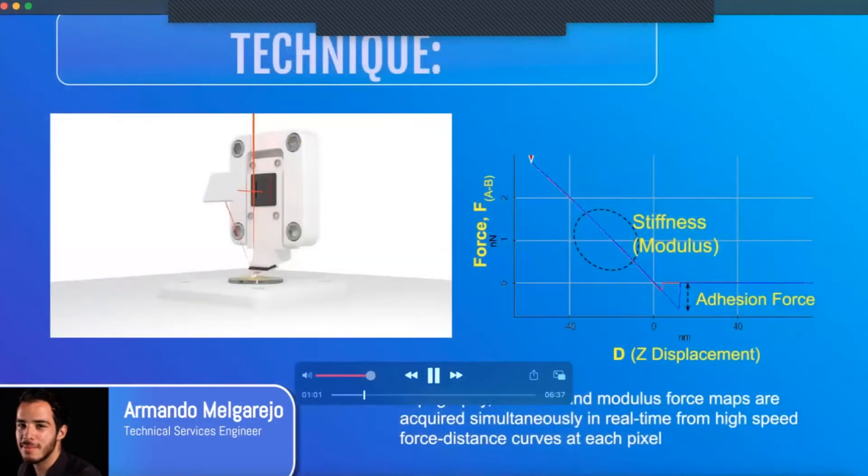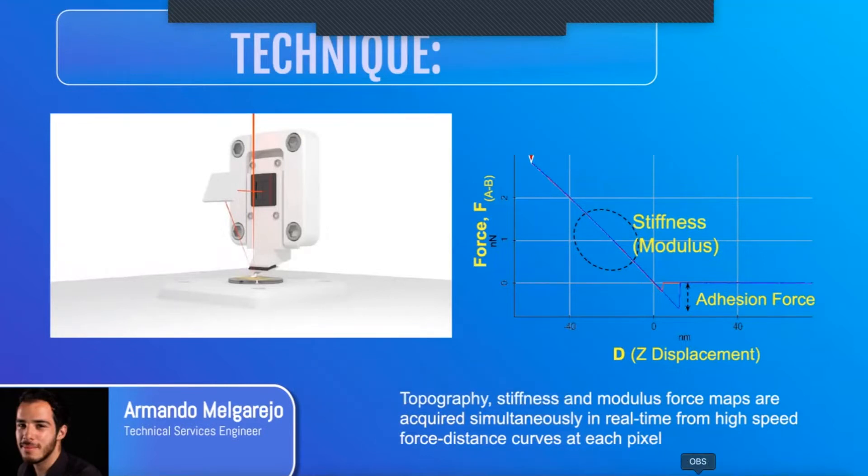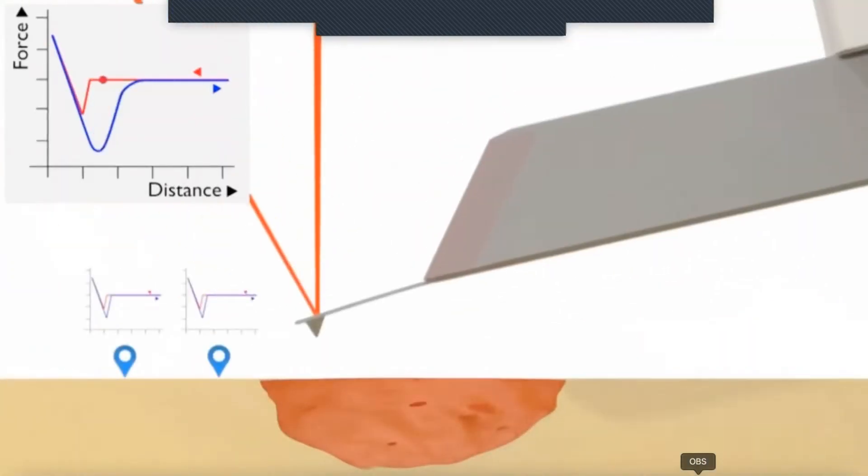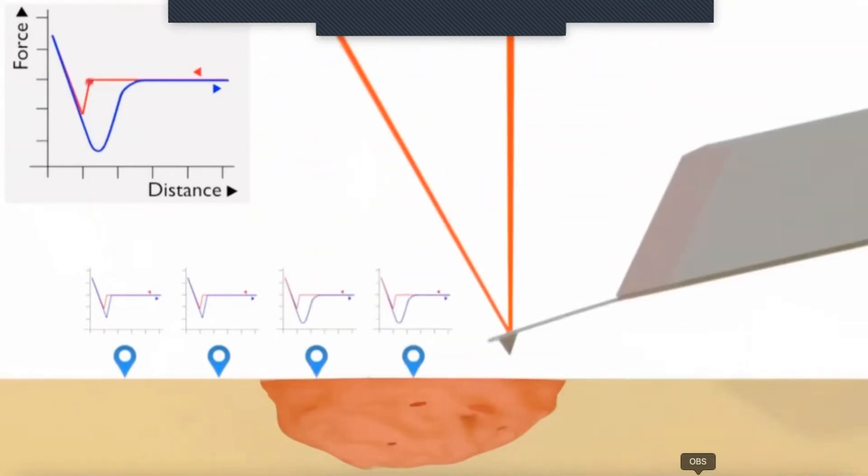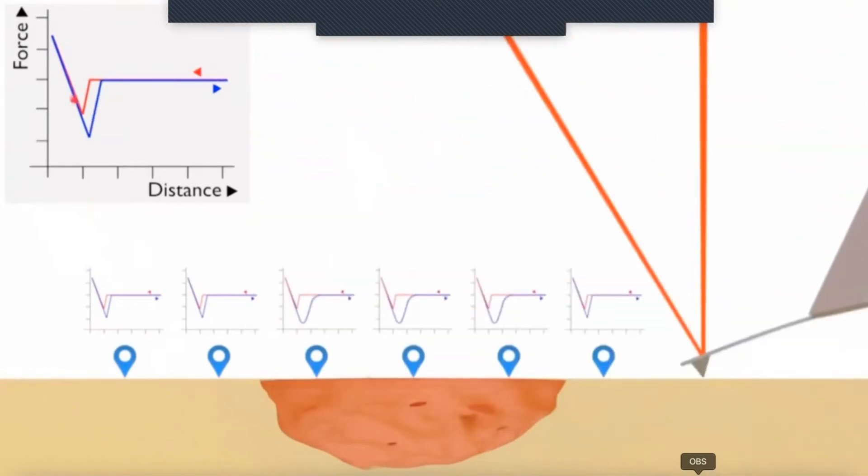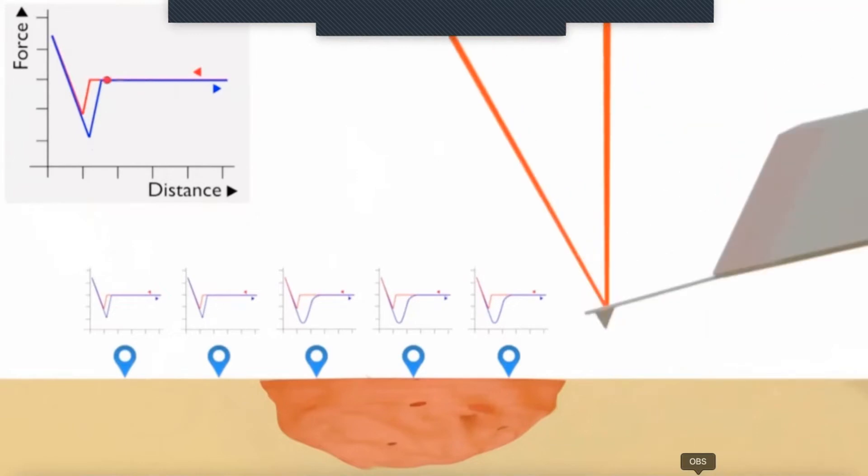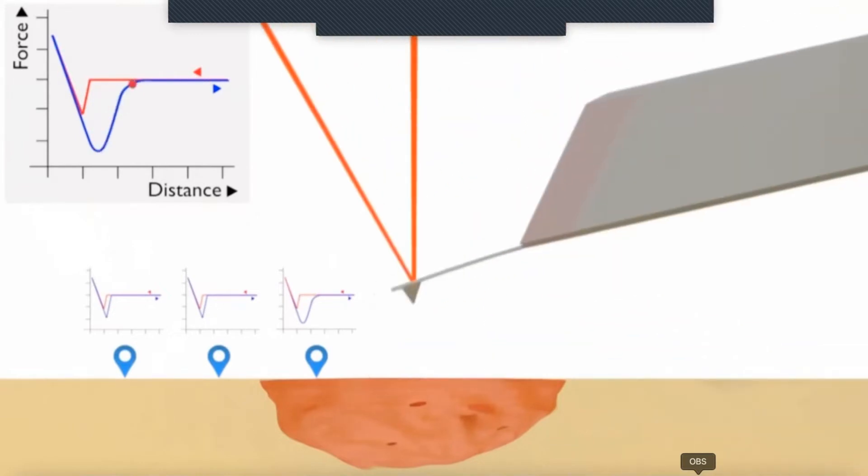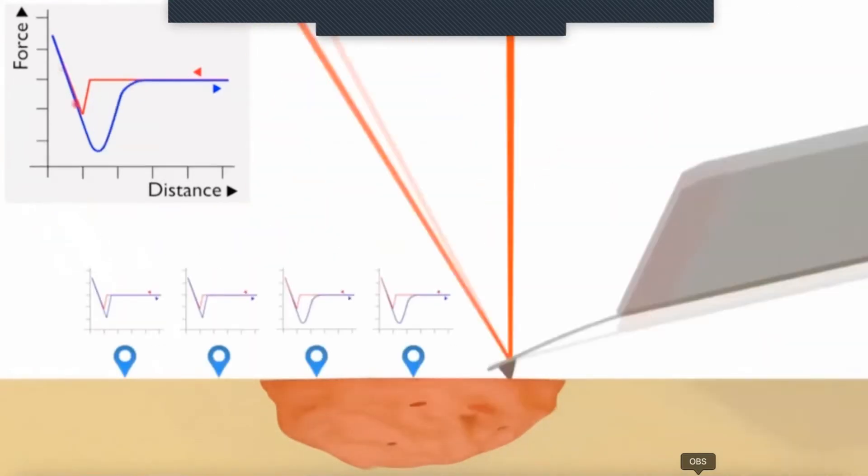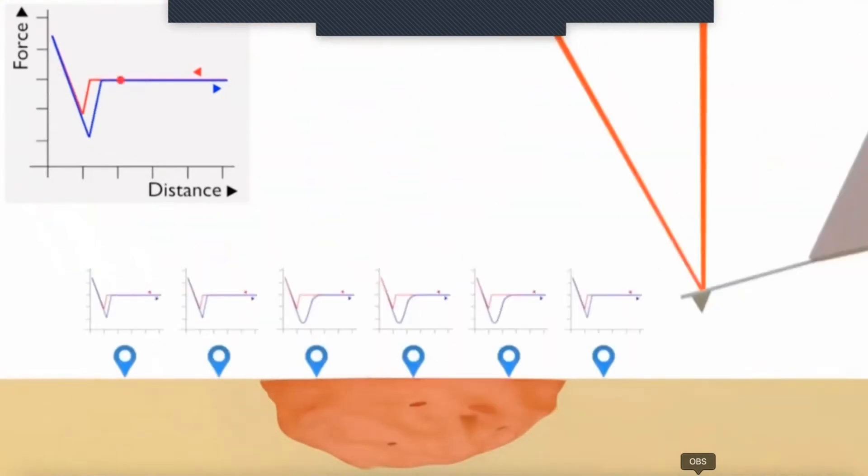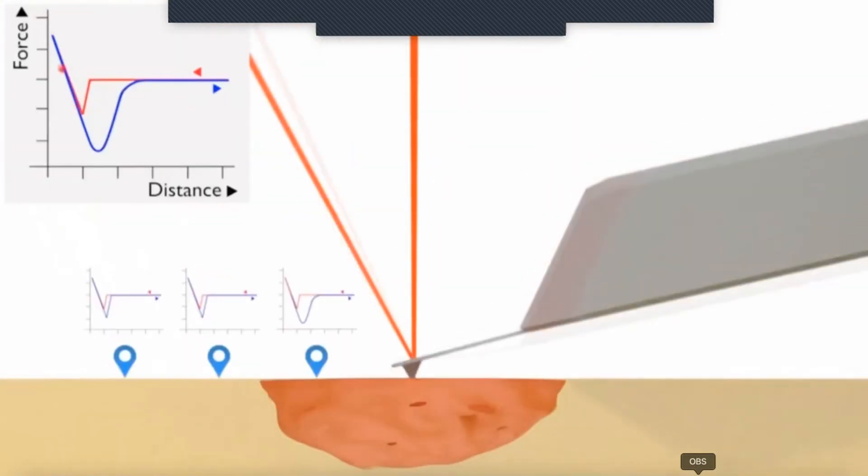To acquire the two-dimensional hardness map of the sample, I will apply the Park PinPoint Nanomechanical AFM mode. The advantage of this technique is twofold. First, it can process the data quickly, and second, it acquires data without lateral friction between the probe and the sample. Consequently, this minimizes the tip wear and retains the probe's shape and quality, ensuring the repeatability and accuracy of the data.